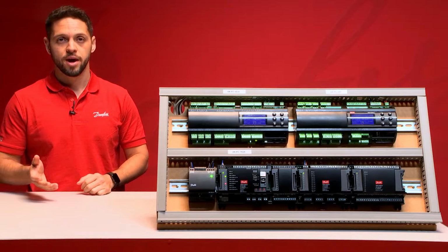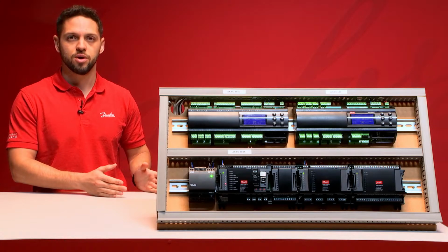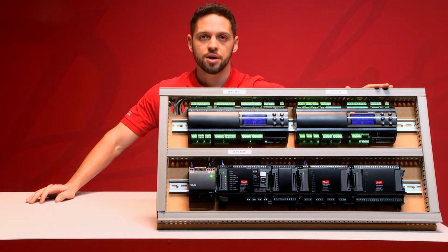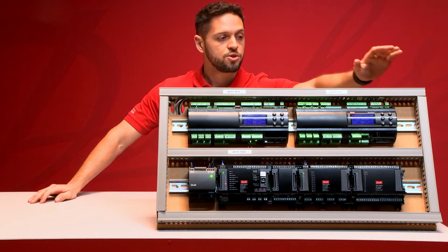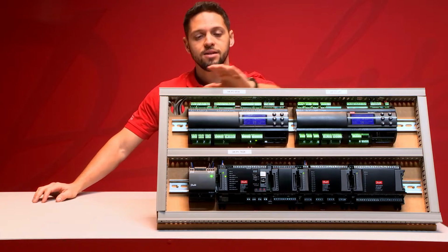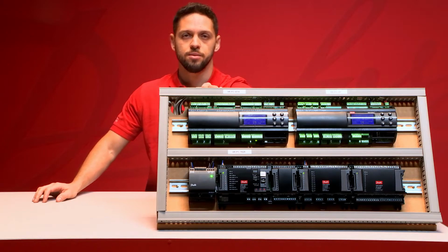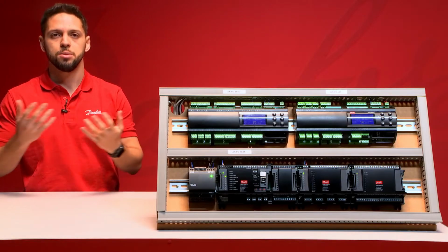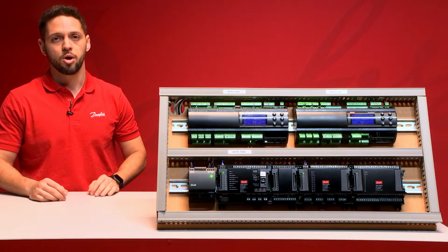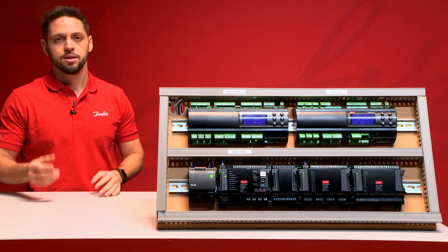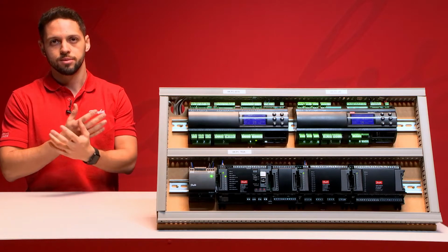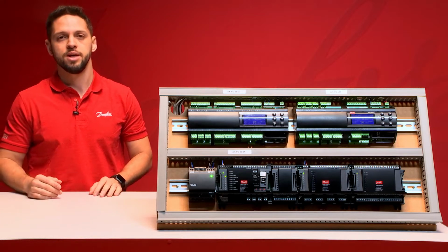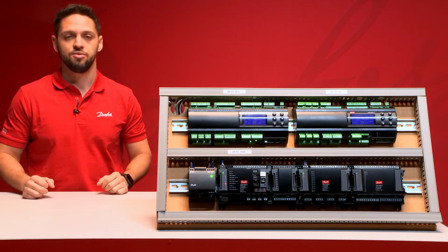As you can see, we have upgraded the AKPC 651 to turn it into the new AKPC 651A. I have installed here both hardwares for comparison. So this is the AKPC 651 and this is the new AKPC 651A. So as you can see, they are very similar. And if you need to exchange both controllers in an installation, probably you won't have bigger problems because the hardware is so close to each other. So you won't need very big changes in the wiring, which makes it very flexible to replace if necessary.